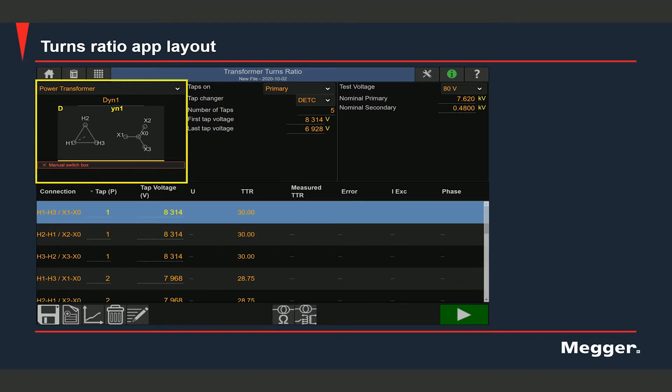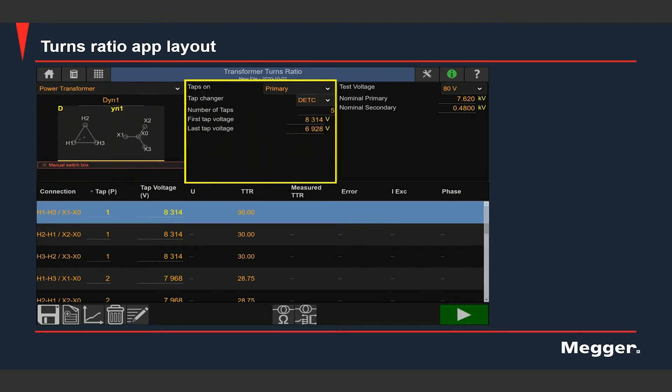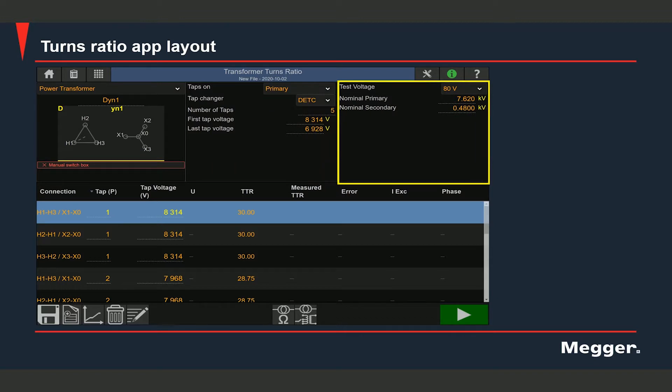In the upper half of the screen, you will need to enter certain relevant information before you start the test. You will need to select the vector group here and you will be able to see the vector diagram corresponding to that group. Here you will need to enter information about the taps: which winding has the tap changer, what's the tap changer type, how many taps are there and the extreme tap voltages. Here you will select the test voltage. The test voltage can be selected by clicking on that dropdown and you can go up to a maximum of 250 volts. You will also need to enter the rated voltages for both windings.